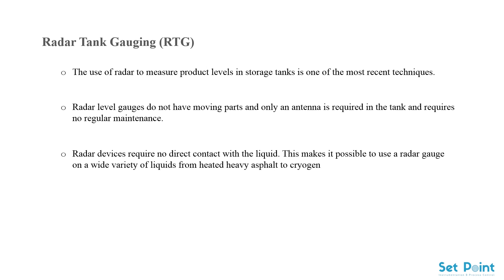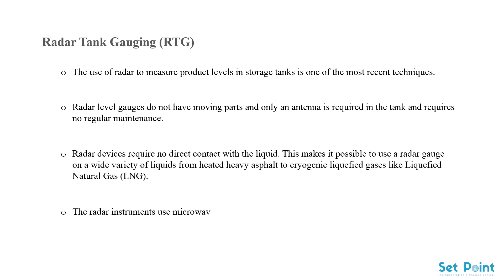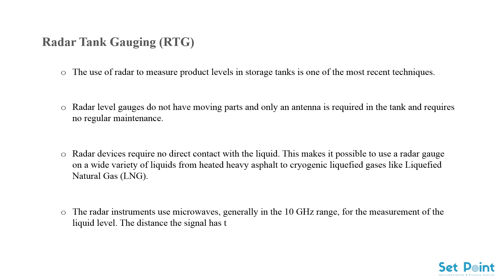This makes it possible to use a radar gauge on a wide variety of liquids, from heated heavy asphalt to cryogenic liquefied gases like liquefied natural gas (LNG). Radar instruments use microwaves generally in the 10 GHz range for the measurement of liquid level. The distance the signal has traveled is calculated from a comparison of transmitted and reflected signals.